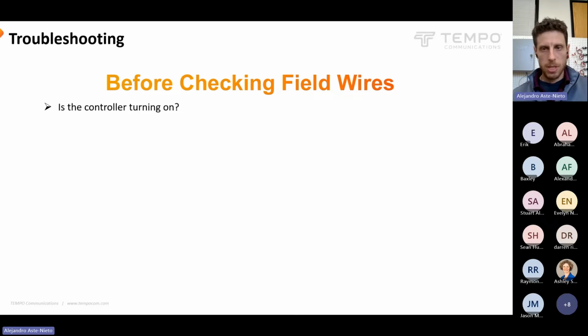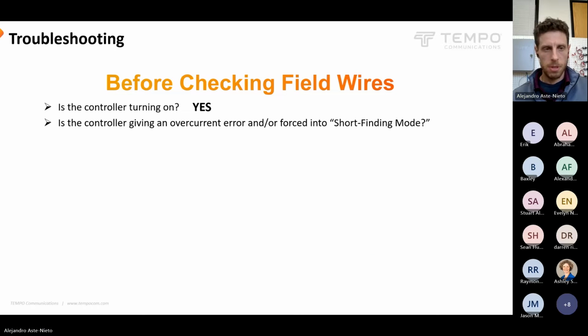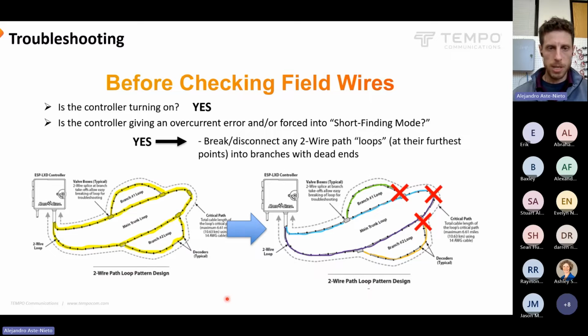So if the controller is turning on, we want to just kind of see what new information it's giving us now. Is there an overcurrent error? Is it just sort of forced into that short finding mode and telling us, yes, there's a short out there, there's an overcurrent happening? If so, we want to break any loops that there might be in the system.